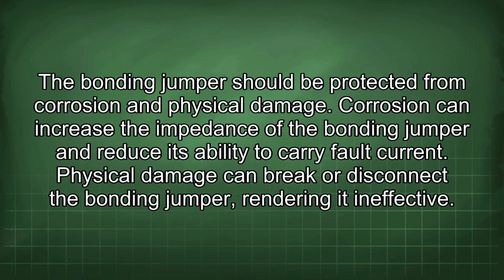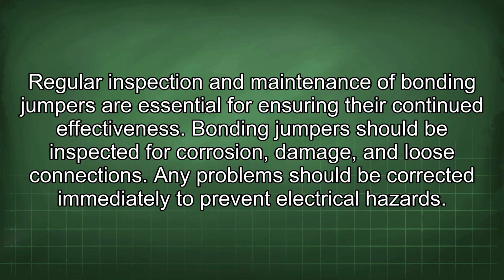The bonding jumper should be protected from corrosion and physical damage. Corrosion can increase the impedance of the bonding jumper and reduce its ability to carry fault current. Physical damage can break or disconnect the bonding jumper, rendering it ineffective. Regular inspection and maintenance of bonding jumpers are essential for ensuring their continued effectiveness. Bonding jumpers should be inspected for corrosion, damage, and loose connections. Any problems should be corrected immediately to prevent electrical hazards.